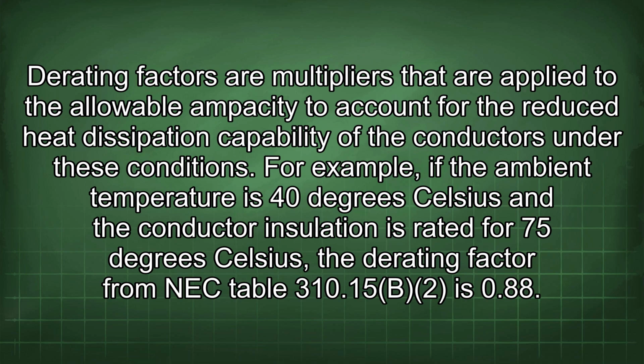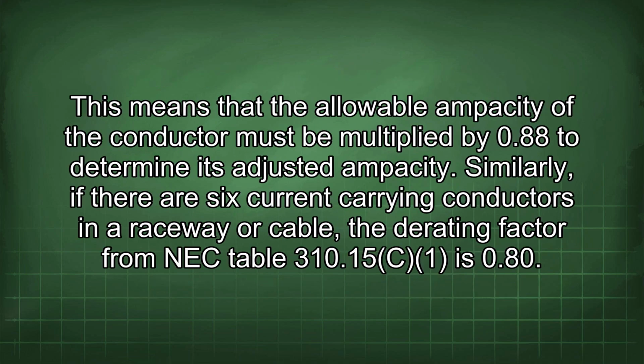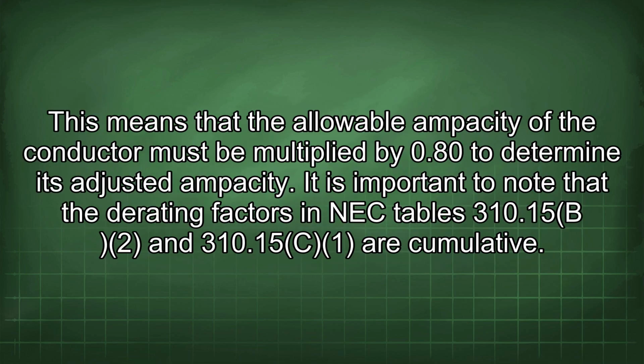For example, if the ambient temperature is 40 degrees Celsius and the conductor insulation is rated for 75 degrees Celsius, the derating factor from NEC Table 310.15(B)(2) is 0.88. This means that the allowable ampacity of the conductor must be multiplied by 0.88 to determine its adjusted ampacity. Similarly, if there are 6 current-carrying conductors in a raceway or cable, the derating factor from NEC Table 310.15(C)(1) is 0.80. This means that the allowable ampacity of the conductor must be multiplied by 0.80 to determine its adjusted ampacity.